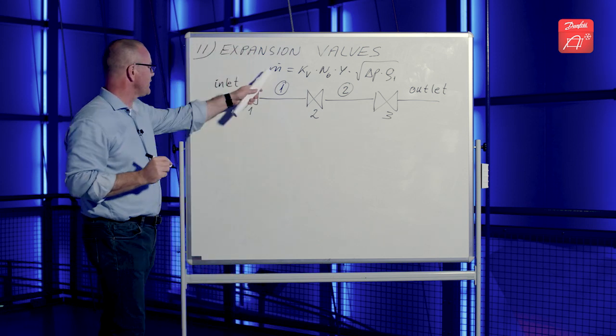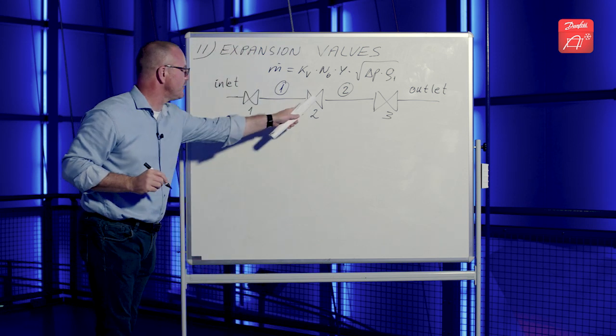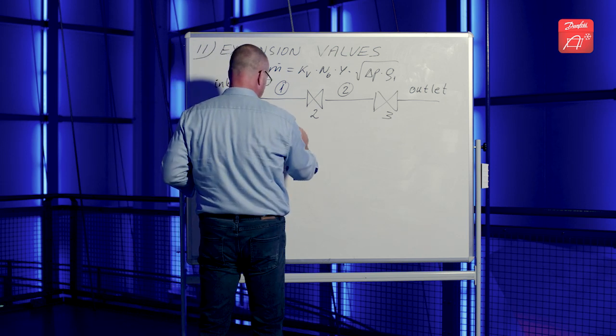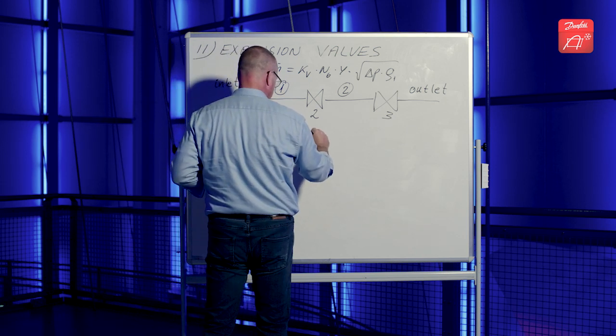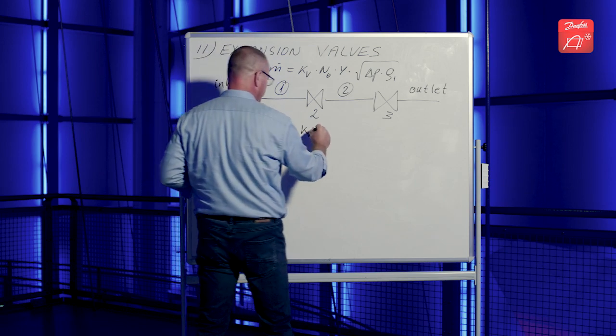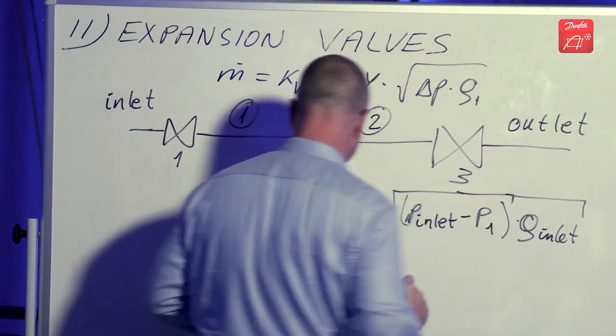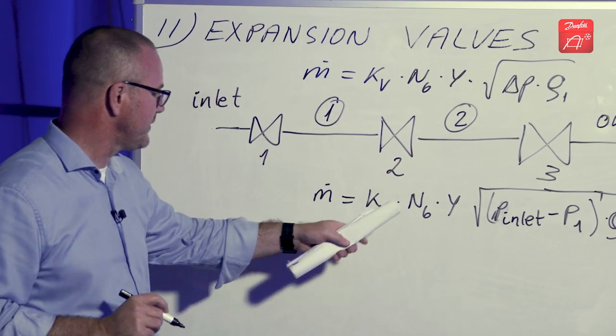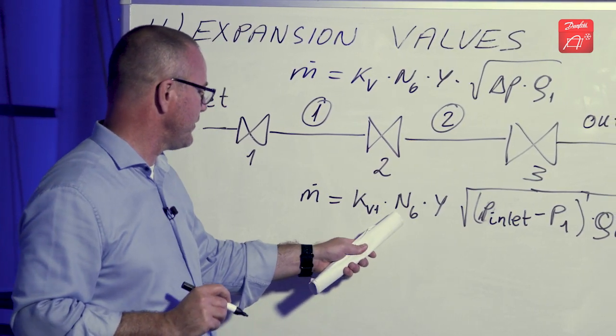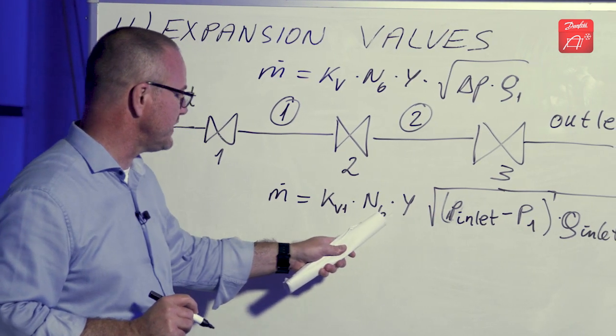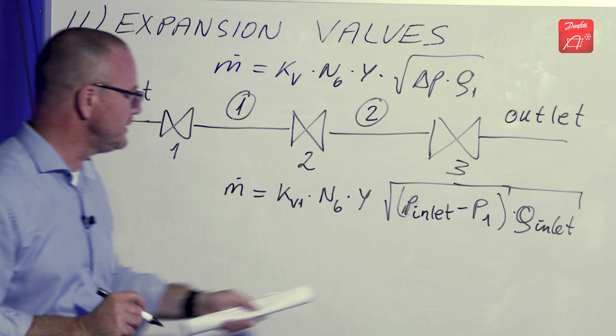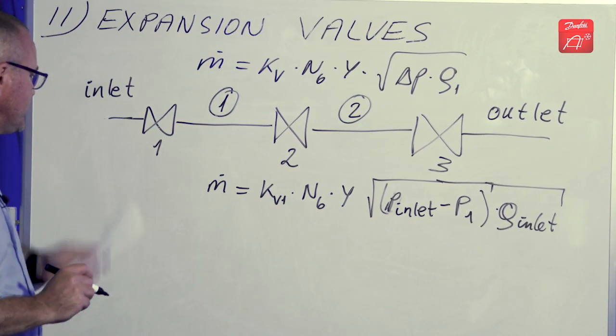So now we write down the valve equation for each of those three valves. So I have mass flow, KV value for the first valve. So for the first valve, we have the first KV value. We have the unit conversion constant. We have the net expansion factor. We have the difference between the inlet pressure and the pressure one and the inlet density.